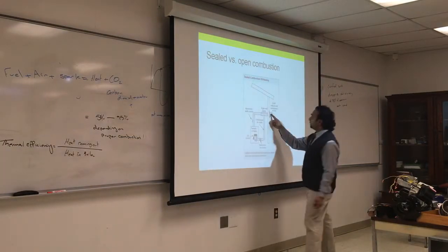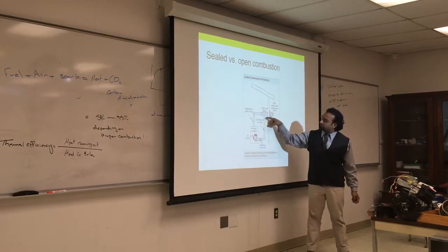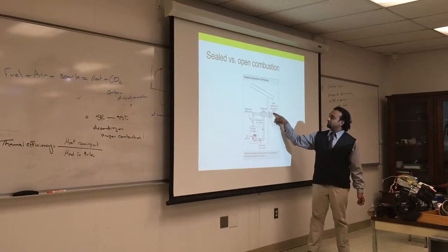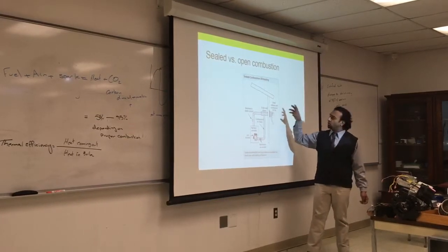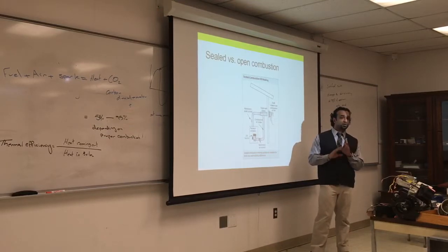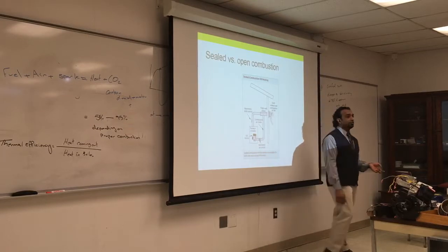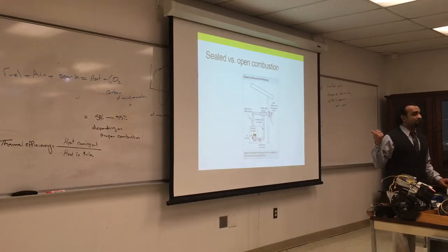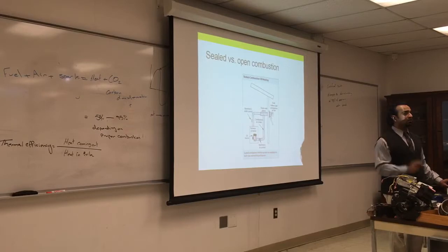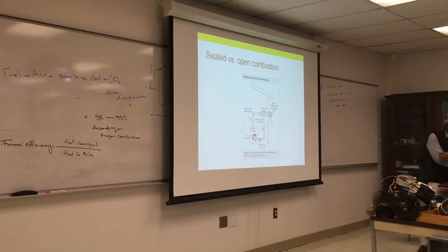Yeah, so now you have only one hole here, which is actually sucking in air going into the furnace for combustion, and whatever comes out goes to the outside. So one hole for both in and out, and we're done with it. The thing is sealed, it's doing its own thing, it does not need anything from the house, and it's a better design. A lot of the European designs actually have that configuration. Wodtke and Viessmann, they're always sealed. I think it's the best way to do it instead of dealing with the house stuff.